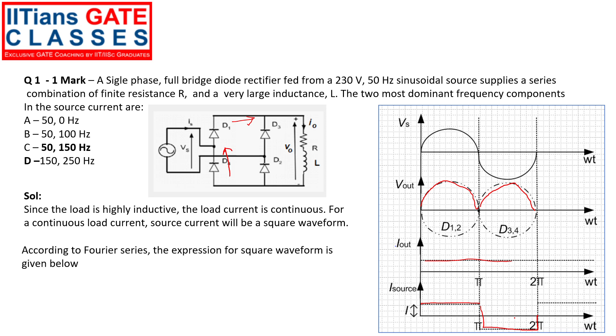According to the Fourier series, the expression for the square waveform is: i_source = Σ (n=1,3,5,...) [4I / (nπ)] sin(nωt), where I is the peak value. From this expression it is clear that we have only odd harmonics: 1, 3, 5, and so on. They are asking for the most dominant frequency components, so the two most dominant are the 1st and 3rd harmonics, that is 50 Hz and 150 Hz.